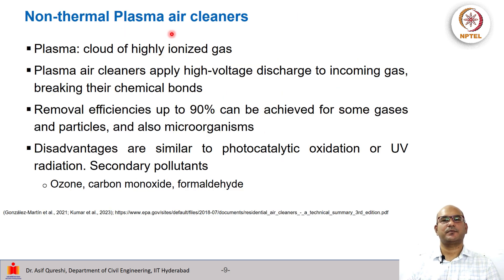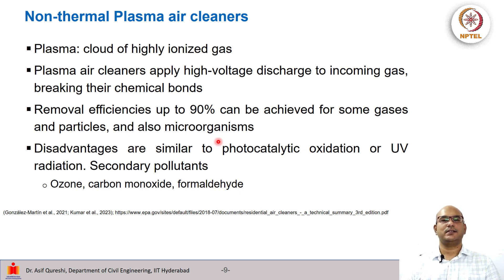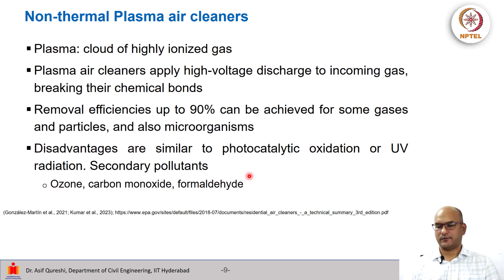Then there are plasma air cleaners. Plasma can be seen as a cloud of highly ionized gas. These plasma air cleaners apply high voltage discharge to the incoming gas, which may break the chemical bonds of the pollutant. Removal efficiency of up to 90% can be achieved for some gases and particles, and these can also remove microorganisms. However, the disadvantages are similar to photocatalytic oxidation and UV radiation, as these processes can again lead to formation of ozone, and sometimes CO and formaldehyde.